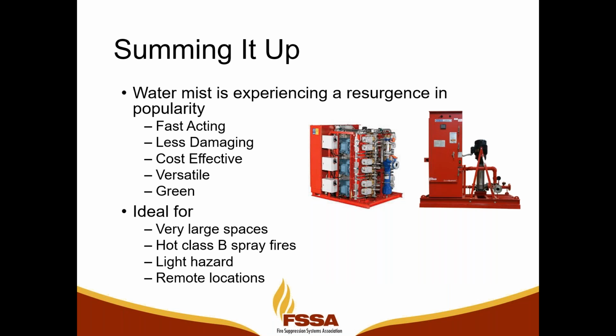Next slide. So just summing up everything you've heard today, if you talk to any manufacturer or installer of water mist systems, I think unanimously we would say that water mist has experienced a renaissance in the past 5 years or so. We've seen more systems come on board with different features, and we've also seen the education curve finally start to take hold among AHJs and specifying engineers. They're starting to understand that water mist systems are faster acting than sprinkler systems because we're using automatic detection in those machinery spaces and turbine enclosures. They're less damaging. We're going to put out 50% less water in a light hazard environment and up to 90% less in a machinery space.